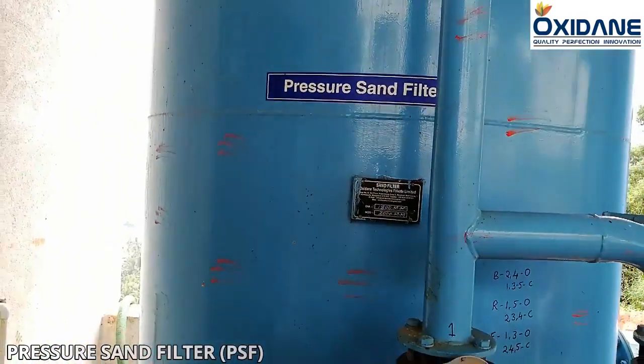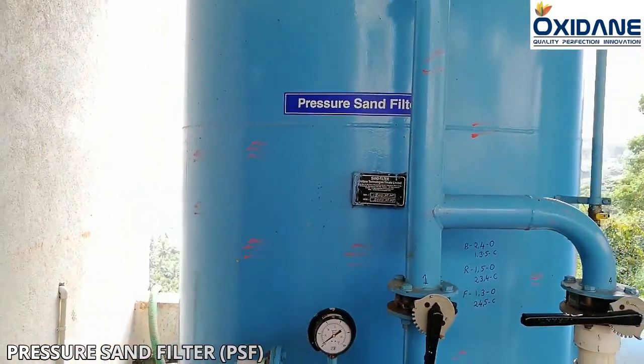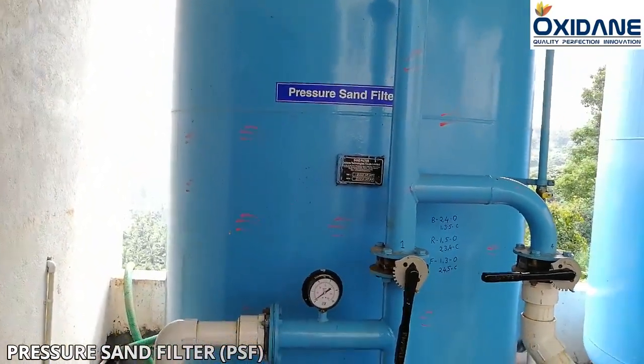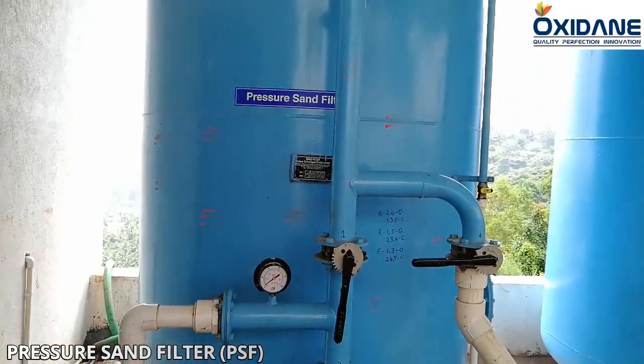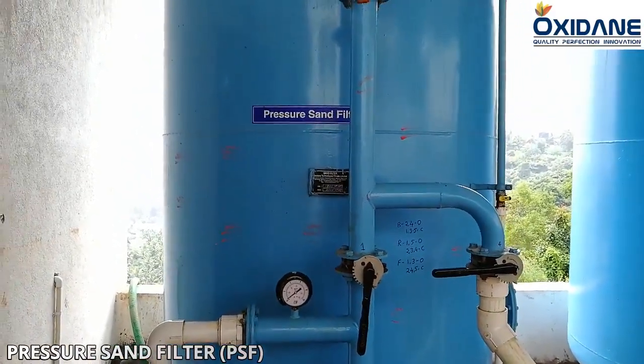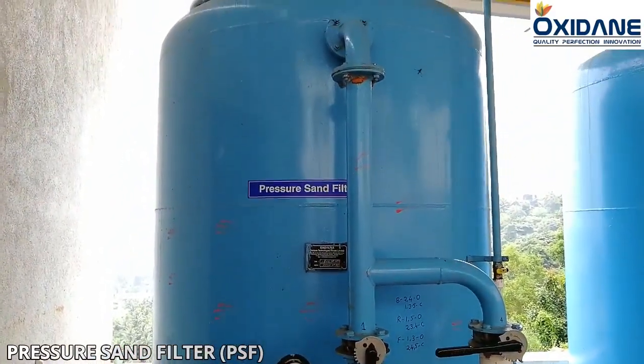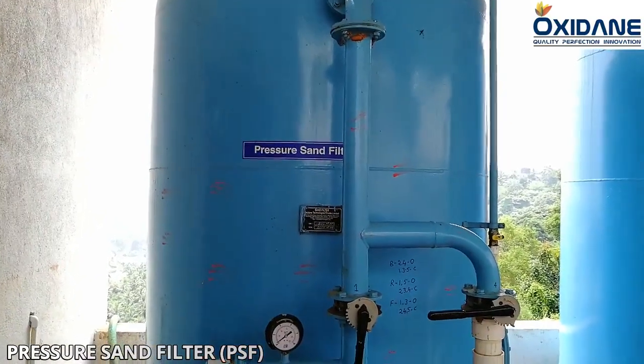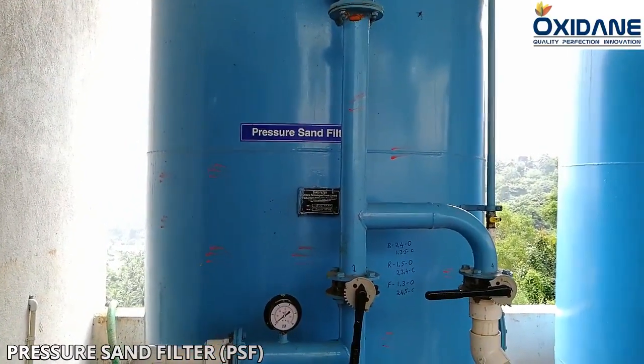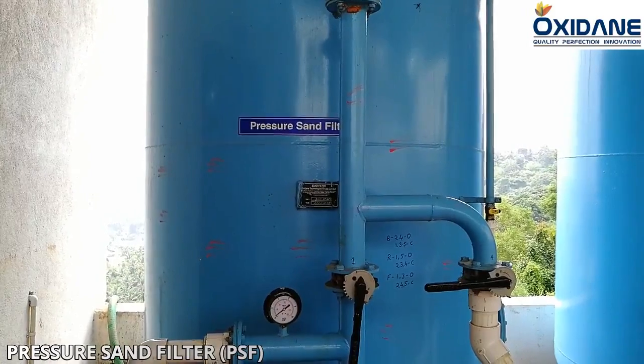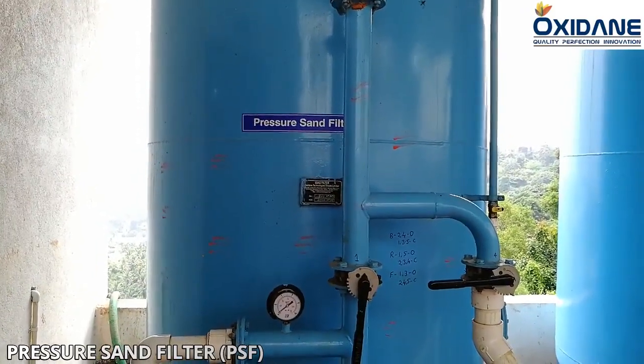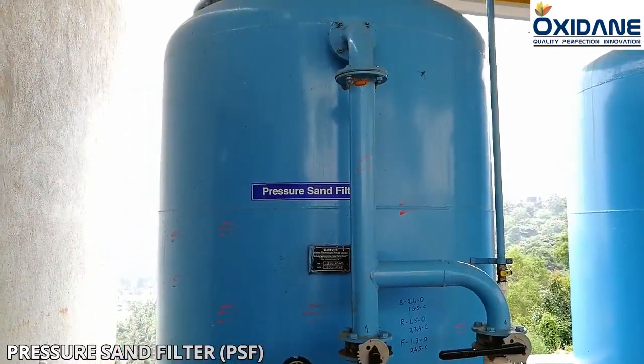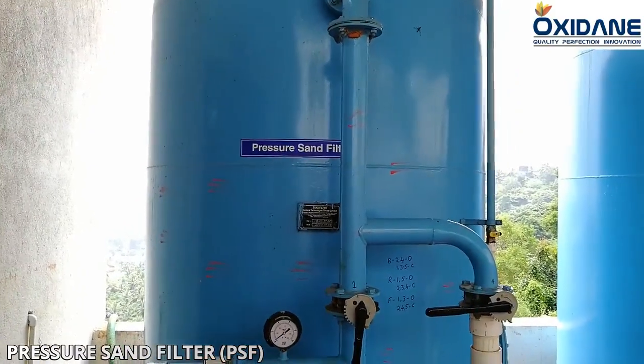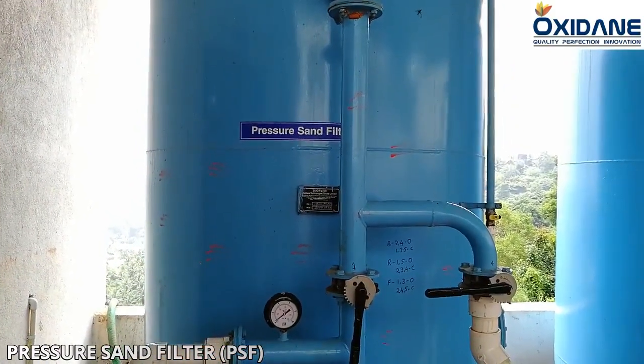Pressure sand filter, or PSF for short. It consists of a pressure vessel, either vertical or horizontal, with a set of frontal pipework and valves. Graded silica quartz sand supported by layers of graded underbed consisting of pebbles and gravels. A top distributor to distribute the incoming water uniformly throughout the cross-section of the filter. These filters are the most popular method for removal of turbidity from water.